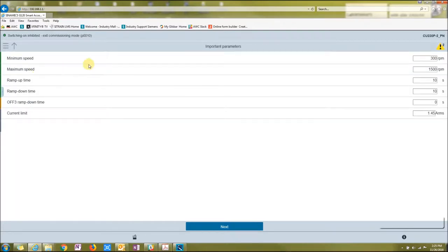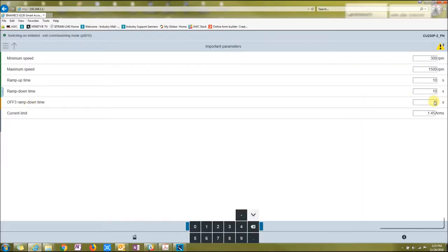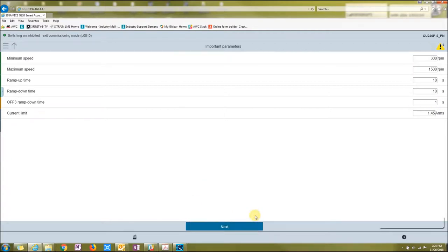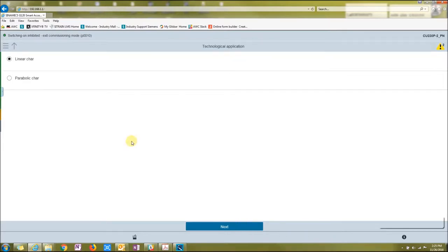This is your minimum speed, maximum speed, seconds up, seconds down, ramp downtime. I don't want it to be zero. I'd rather that be one, so at least it has a little bit of time before it shuts down. And then there's a current limit. Say next.